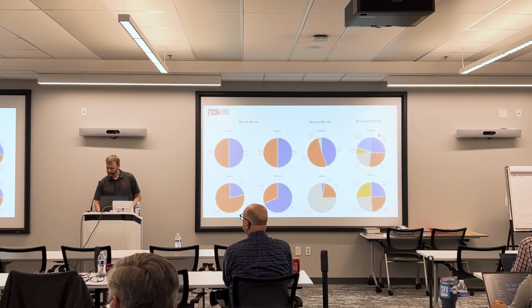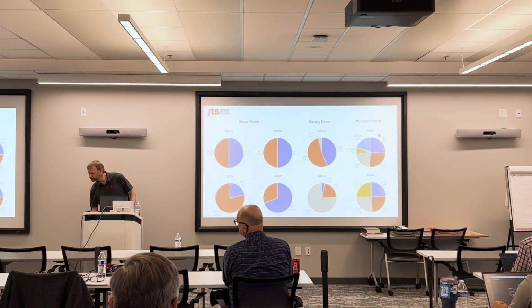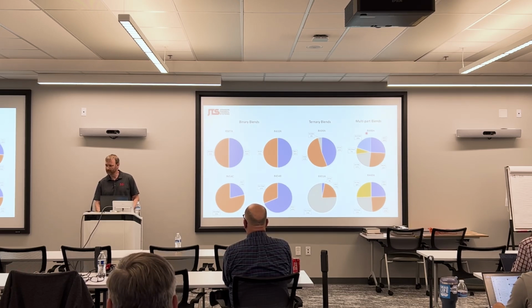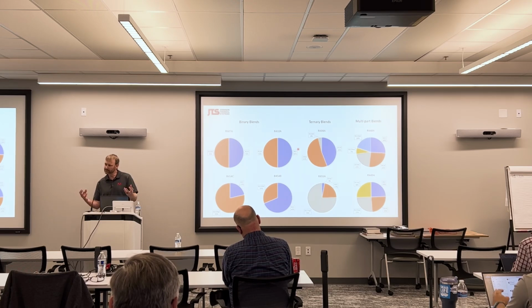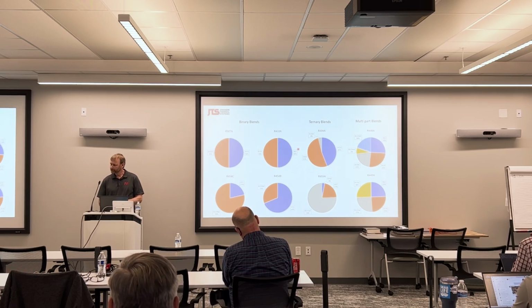Can you repeat that? Are they used as A2Ls or no? What's that? A2Ls? Yeah, R32 is an A2L, but when you make the blend, they don't consider it A2L. If you're mixing, like 410A for instance, it is an A1 refrigerant, because it's mixed A2L with a fire suppressant component. Is the fire suppressant component still in the refrigerant? It is, yeah. R125.